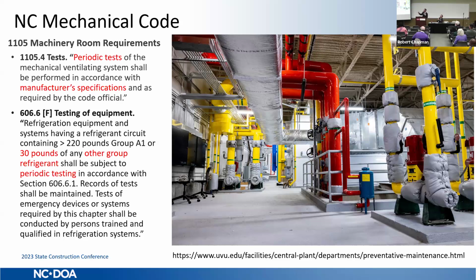If you transition to the higher efficiency, newer A2L refrigerant systems, look at what it drops down to. It drops from 220 pounds down to 30 pounds where you're required to do those tests. The reason for that is it's so much more flammable than the other refrigerant. And in doing so, it also changes the hazard classification of the mechanical room that it's in. So when you take on a project like this, you want to make sure that you address the hazard classification, Class 1, Div 2. And then you have all the existing circuiting that goes through there. You have to make sure that that circuiting is also changed so that it can comply with the new hazardous location based on the newer efficiency of the refrigerant.